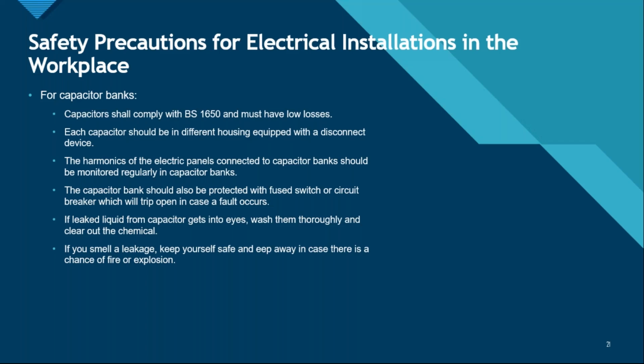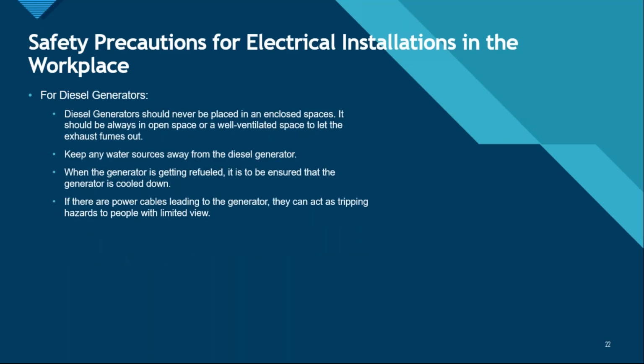If you smell leakage, keep yourself safe and keep away in case there is a chance of fire or an explosion. Diesel generators should never be placed in enclosed spaces. Like we discussed, they have a diesel engine which will be producing fumes, basically carbon monoxide. So if it's in a closed, confined space, there can be too much carbon monoxide. The people working around might suffocate as a result of it. It should always be in an open space or a well ventilated space to let the exhaust fumes out.